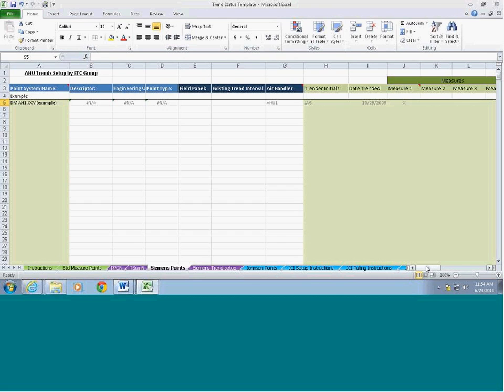So finally, you again narrow down your list of problems. You move back one more step. Go back to the raw CSV file and make sure for this point name, is it in this file at all? I assume there is a file because we had other data. Any data at all, maybe that's still missing. But sometimes what you see when you look in that report is that it did actually try to get a point, but there's no data. So it didn't narrow down your results.